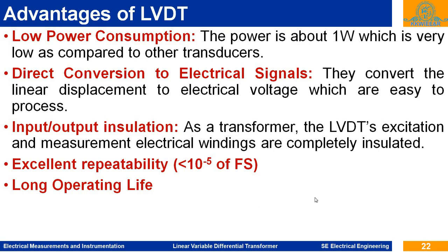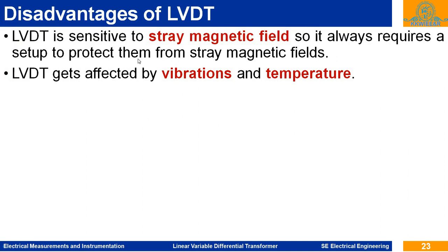Low power consumption, so there is no heat, and losses are very less. So overall, this will improve the operating life of the LVDT. What are the disadvantages? The LVDT is sensitive to stray magnetic fields, vibrations and temperature. For stray magnetic fields, we provide a steel container for the LVDT to minimize the stray magnetic field.